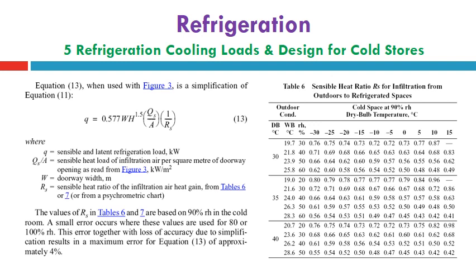over RS, which is the sensible heat ratio of infiltration air heat gain, which can be taken from table 6 attached to this slide, or table 7 attached to the next slide, or from the psychrometric chart, which can be used for AC applications to detect the specific heat ratio or sensible heat ratio based on the temperature of dry bulb and wet bulb and the relative humidity inside the cold space, which is commonly taken as 90% relative humidity. So the wet bulb is commonly near the dry bulb, such that the relative humidity is about 90%.